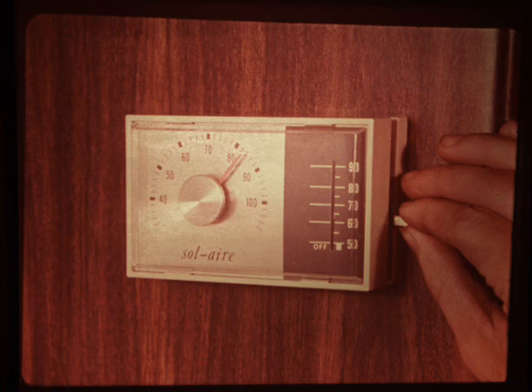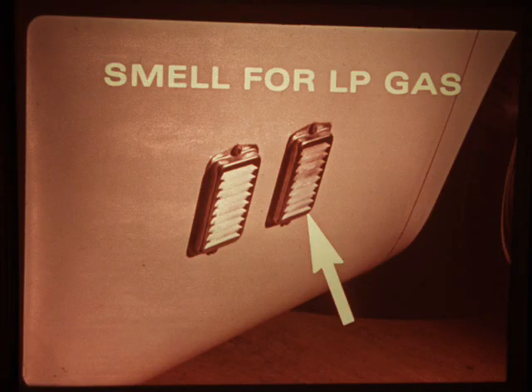Walk outside the coach. You have about 30 seconds before the reset pops. And smell for LP fumes at the exterior right-hand furnace vent. If the solenoid gas valve opens, gas will flow through. If you don't smell gas, it's because the solenoid gas valve didn't open. We'll see what to do about that in a minute.